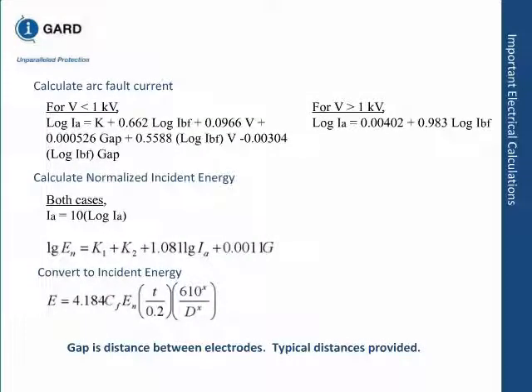This is an equation that appears in IEEE 1584, which is considered the best available standard as of now for calculating incident energy. I will not go through all the equations, but you can see that it requires some calculation. One thing is working distance. You need the working distance, where you are going to work. People say we do not have a problem because we work too far, but sooner or later you have to come close to the equipment. And the gap is the distance between electrodes.